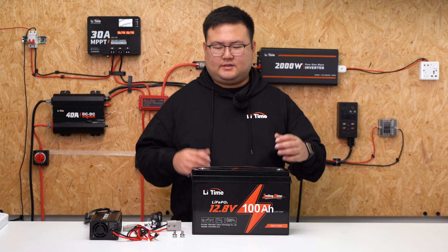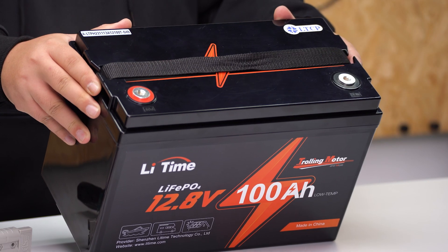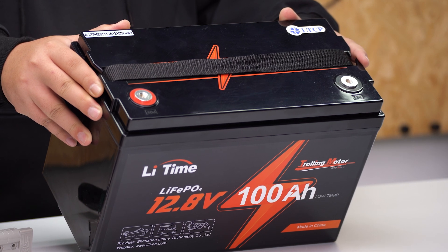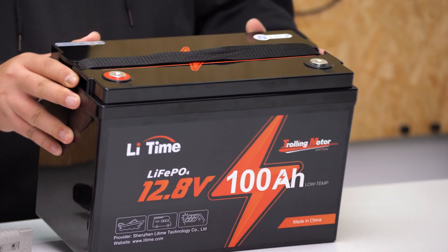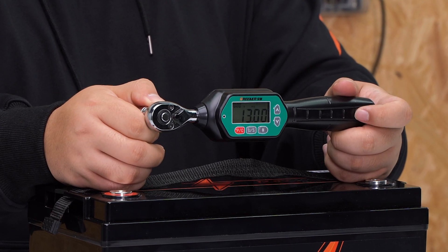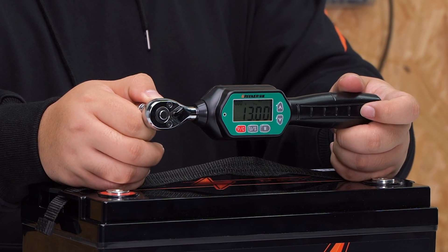Now let's conduct the charging test. On your battery, you will see the red terminal is the positive terminal and the black one is the negative terminal. Set your torque wrench — for this particular battery, we recommend setting the torque wrench to 12 to 14 Newton meters.